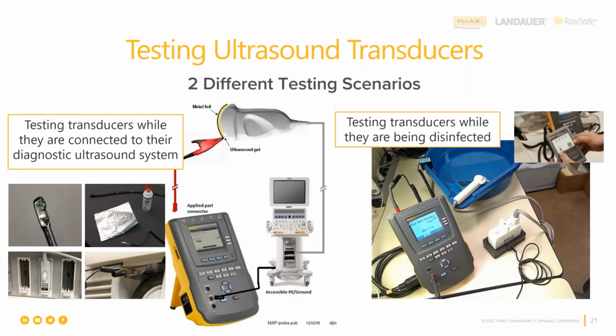Well, what about this transesophageal echocardiographic probe? This is a really important situation, because this transducer, an ultrasound transducer, is inserted down the esophagus of the patient, and it's going to take an ultrasound image of the heart from right behind the heart. What you need to know is that right behind the transducer face is between 400 and 800 volts of push, electromotive force. All we need is just a little bit of resistance for that electromotive force to develop a current that would overwhelm the very, very tiny currents in the heart. And so we don't want to risk that.